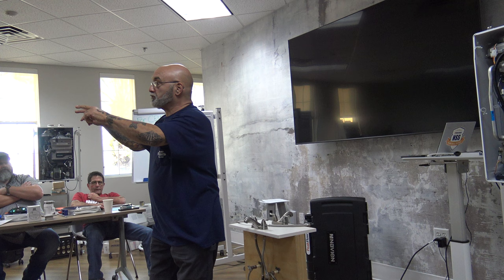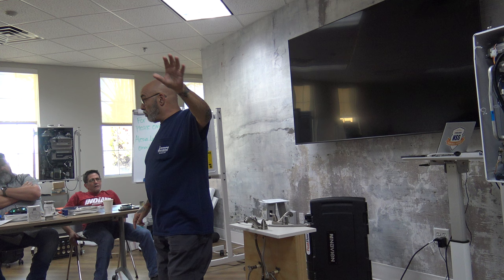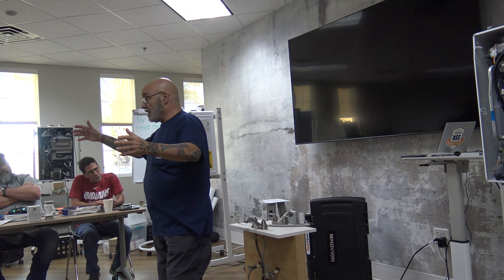You want to see a perfect example of bad venting? When you walk out this building, look to the left, and look at the 4 Rinnai vents sticking out of the wall. There's white and black. There's a black thimble and black vent. Are you familiar with Rinnai's venting? Yeah. Well, that white is not UV protected. So by having that stick out, you're going to get microscopic cracks and you're not going to get proper air intake.